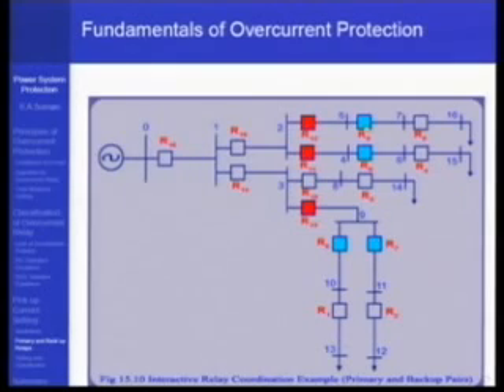Then after that you would set, yeah, so these are the red relays which are set first, then these are the primary relays. Okay, then these relays are set second. I think that is also correct. Then these relays, this has already been set, that's why it's not been shown. So the red relays are the relays which I am showing, the blue relays are the corresponding backup relays for which the backup action has to be provided. Then I am setting these 3 relays. This relay has already been set. Then I set these 2 relays, they back up here, and then I set this relay, they back up here.